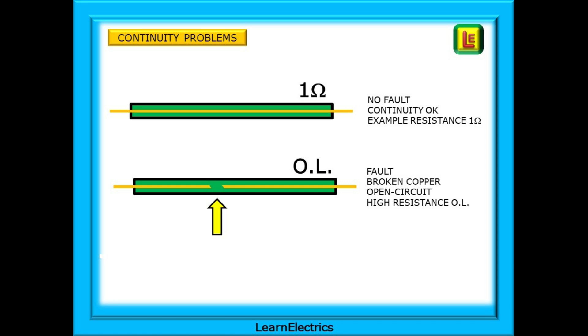A good cable with no fault and with an intact conductor might measure just one ohm. Compare this to a cable where the copper has a break in it - it is said to be open circuit, and it is usually not possible to prove this visually. This is why we must test cables with a meter. My meter shows OL - short for over limit - meaning the resistance reading is so high the meter cannot display it. I call this the fresh air result, for the break in the copper. Some meters will show the meter maximum, possibly several thousand ohms, and the secret is to practice and to know your meter.